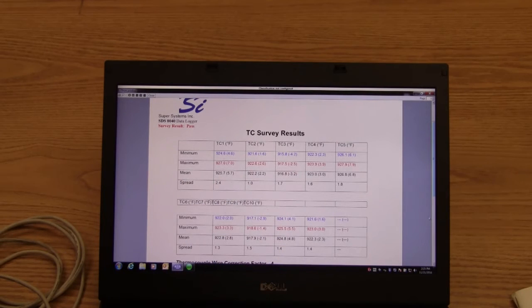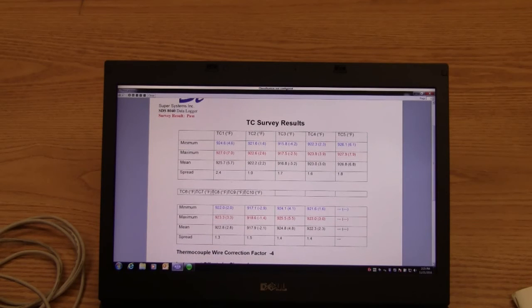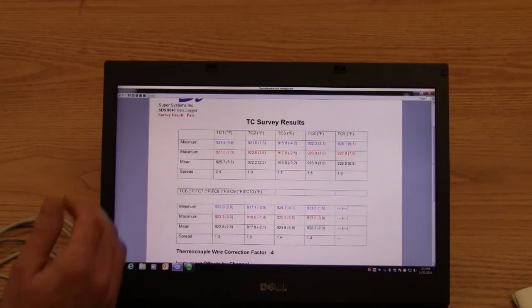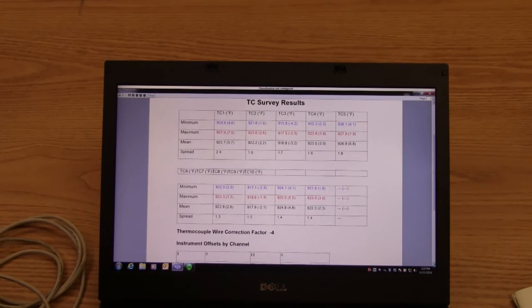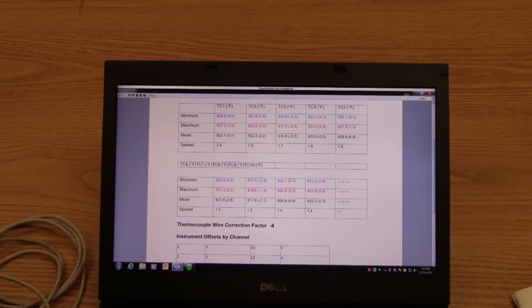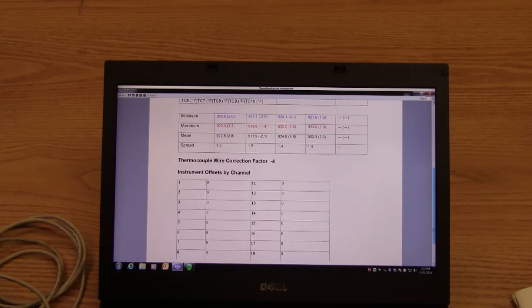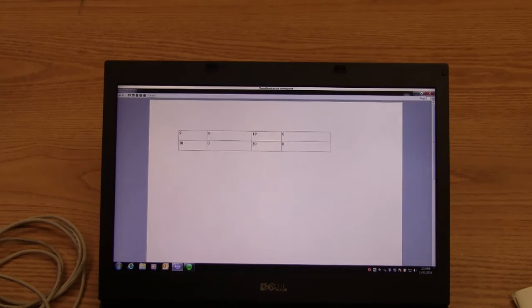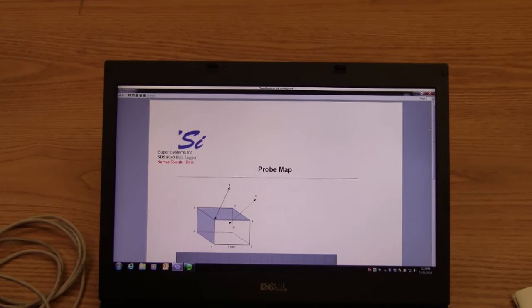This reports back on each individual thermocouple inside your chamber, so you can see any hot or cold spots, or if you have huge temperature swings as your oven cycles on and off. But for these purposes, since our survey was a pass, and pretty well centered really, I'm not too worried about it. So next page again, page 6, that chart was big, carries over.